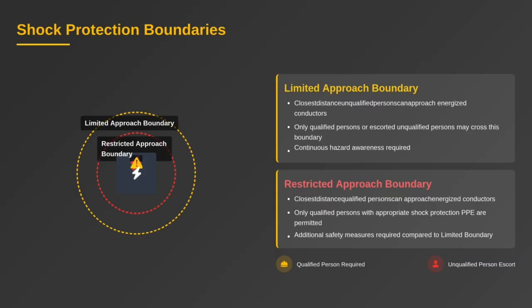NFPA 70E defines 2 key boundaries: the limited approach boundary and the restricted approach boundary. The limited boundary is the closest distance an unqualified person can approach energized parts, and only under supervision. The restricted boundary is even closer, and only qualified workers with full PPE can enter this zone. These boundaries create invisible barriers of protection, keeping workers at safe distances from live conductors.